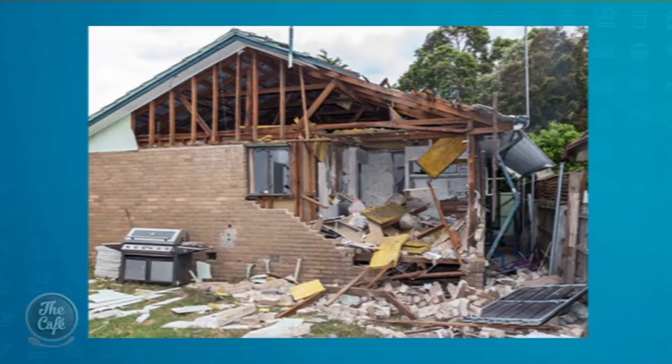Here's an example of when it goes wrong — that damage is from a hot water cylinder. What can happen is the valving around it can stop the expansion of water within the cylinder, so the pressure stays in and keeps building up, then it just has to go somewhere and it goes sideways. You are not kidding when you say it turns into a bomb — and apparently that's not even a bad one, there's much worse.